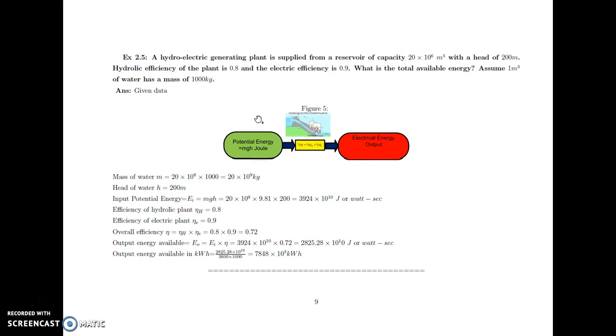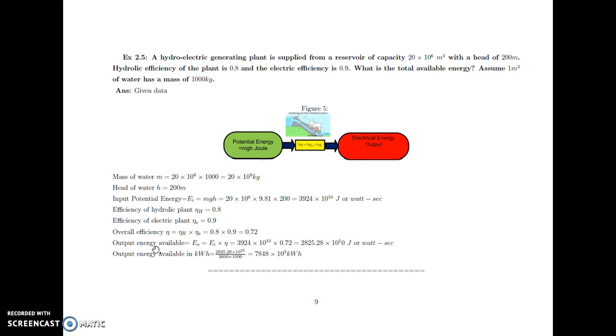The head is 200 metres. We are converting potential energy into electrical energy, so the input is potential energy and the output is electrical energy. Potential energy is equal to mgh — mass into gravitational force into height. Substituting mass, g as 9.81, and height as 200 metres, we get 3924 into 10 raised to 10 joules or watt-seconds. Hydraulic efficiency is 0.8 and electrical efficiency is 0.9, so overall efficiency is 0.8 into 0.9 equals 0.72. Output energy available equals input energy into efficiency: 3924 into 10 raised to 10 into 0.72.